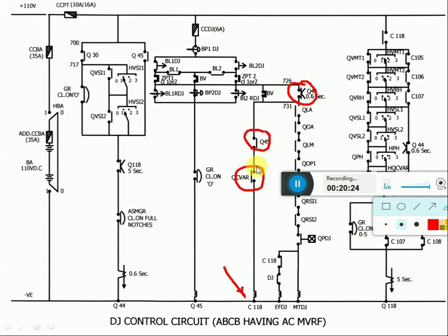So after cleaning these interlocks, try to close DJ and ensure whether C118 is picking up or not. Even after cleaning the interlocks, if C118 is not picking up, try by LT. If C118 picks up on LT but in HT, while closing normally, C118 is not closing, it means the Q44 interlock is defective on the C18 branch. You can clean the Q44 interlocks again.